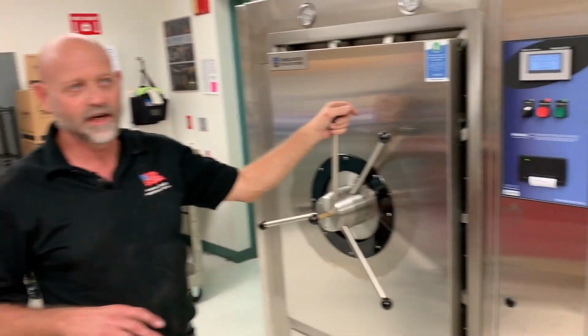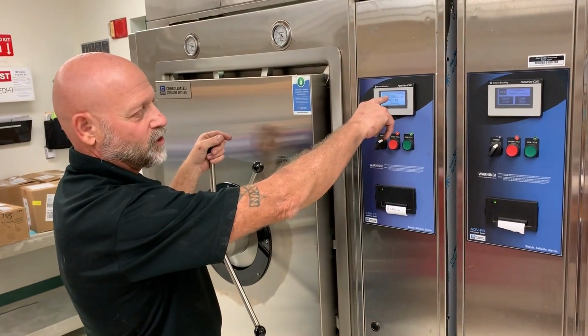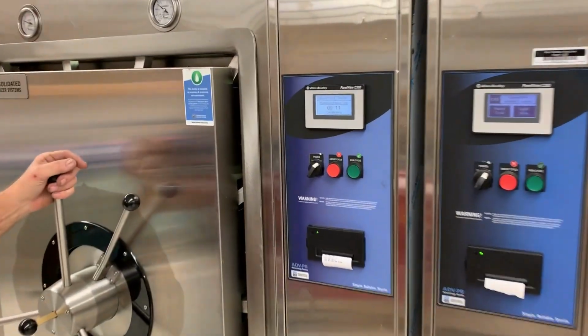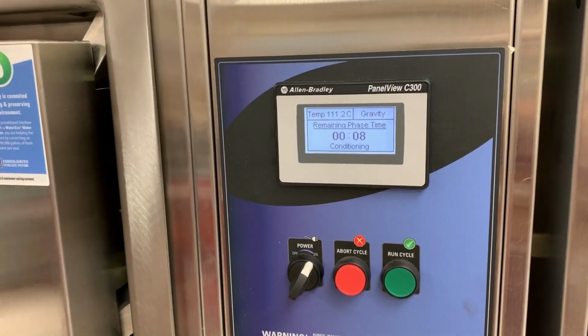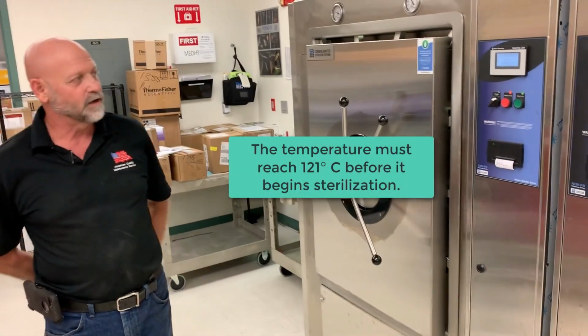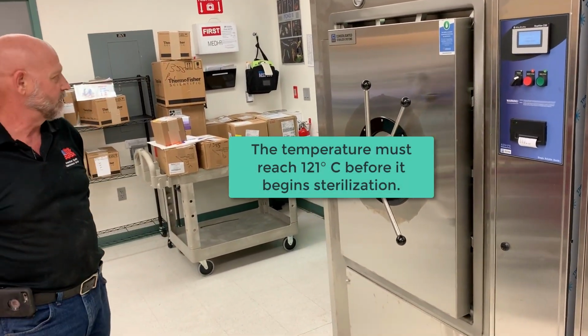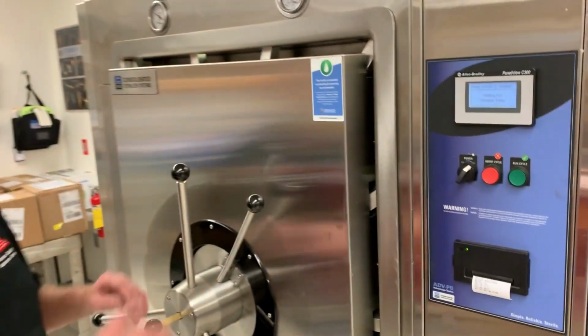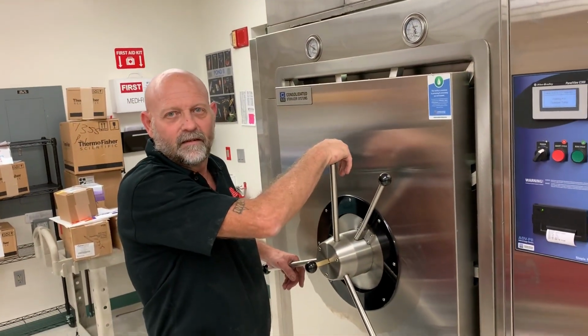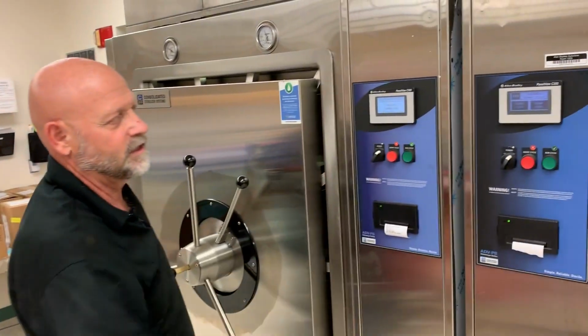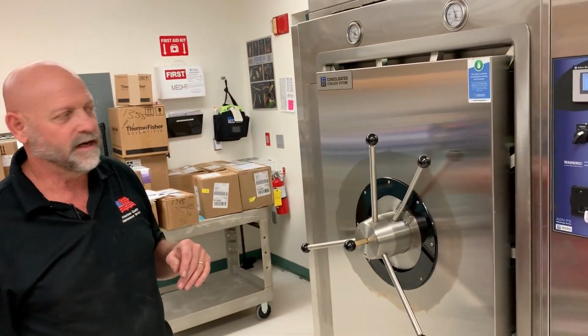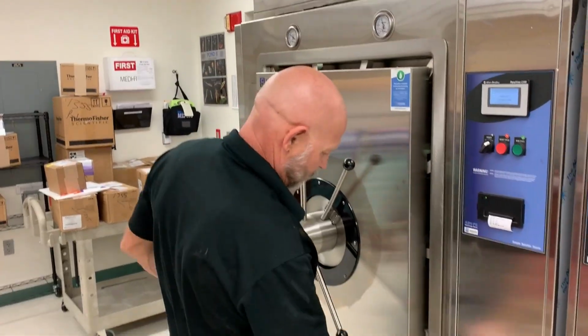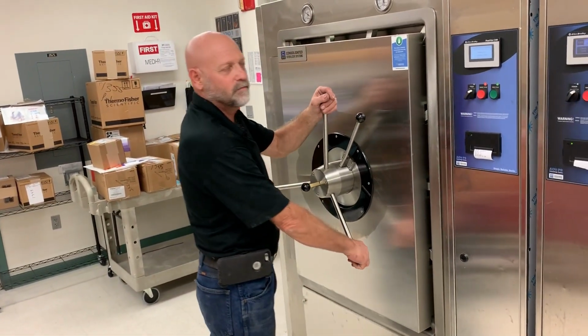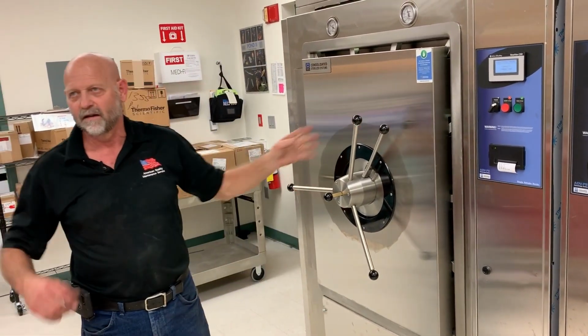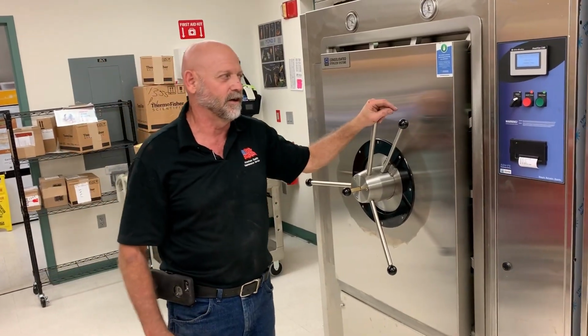As soon as the conditioning is done, you'll notice the temperature really start going up until it hits 121. This could take a minute or two. Got to get up to 121. Now, while this is coming up to temperature, you never want to leave the machine until you see this in sterilization. The reason being, if you hear any leaks around the door, just tighten it a little, just a little bit, to make sure that you got a good seal.